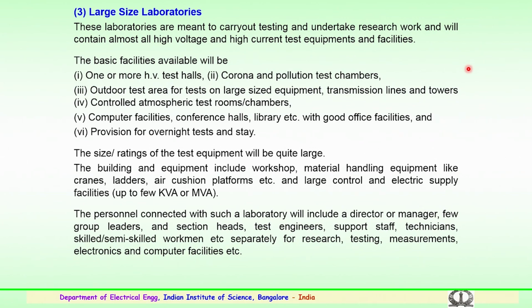There could be an outdoor test area for tests on large size equipment, on transmission line components, and a very large area where the towers also could be tested. Towers have to be tested for mechanical loading and so on. So, this type of laboratory could have facilities for both outdoor and indoor arrangements. The laboratories will have controlled atmospheric test rooms and chambers for conducting experiments, testing or certification of components pertaining to atmospheric condition tests. These laboratories in general will have computing facilities, conference halls, a library with good office facilities, and a provision for overnight tests and also stay. So, these are very large laboratories, certification type laboratories.